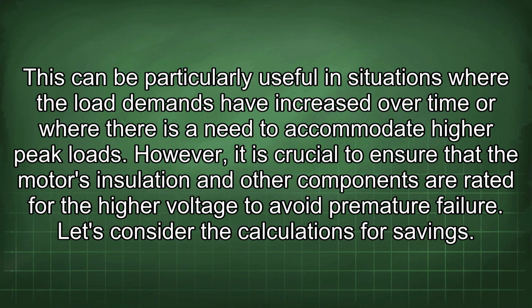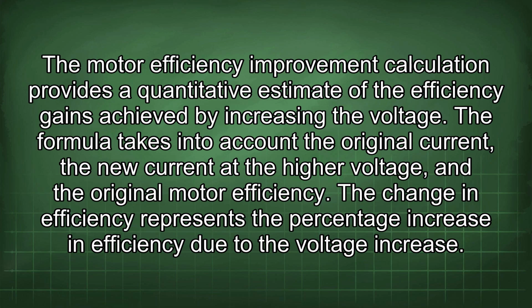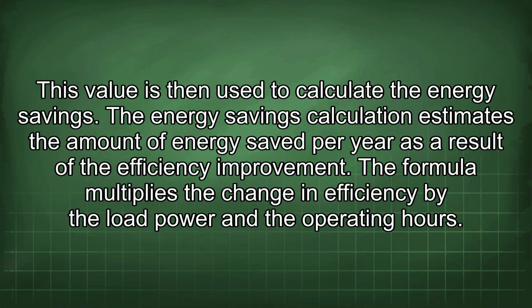Let's consider the calculations for savings. The motor efficiency improvement calculation provides a quantitative estimate of the efficiency gains achieved by increasing the voltage. The formula takes into account the original current, the new current at the higher voltage, and the original motor efficiency. The change in efficiency represents the percentage increase in efficiency due to the voltage increase. This value is then used to calculate the energy savings.